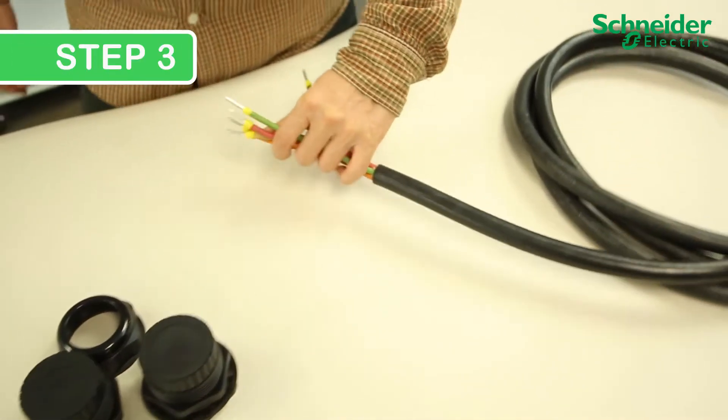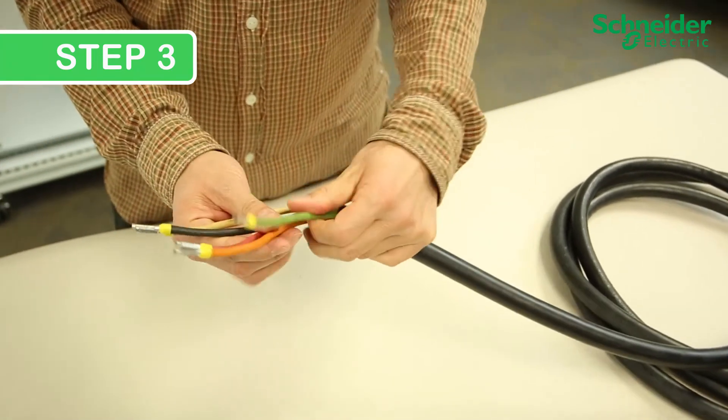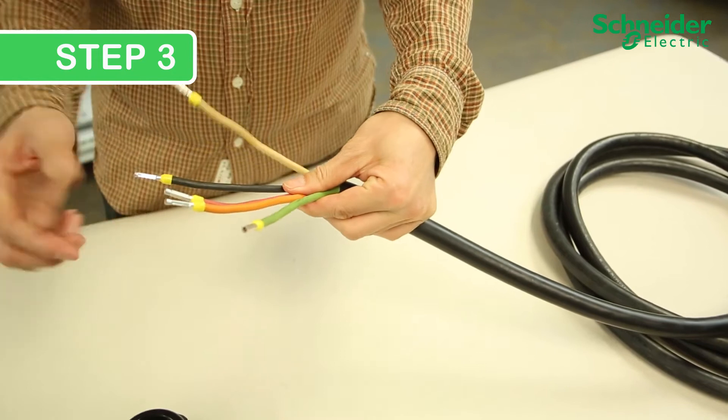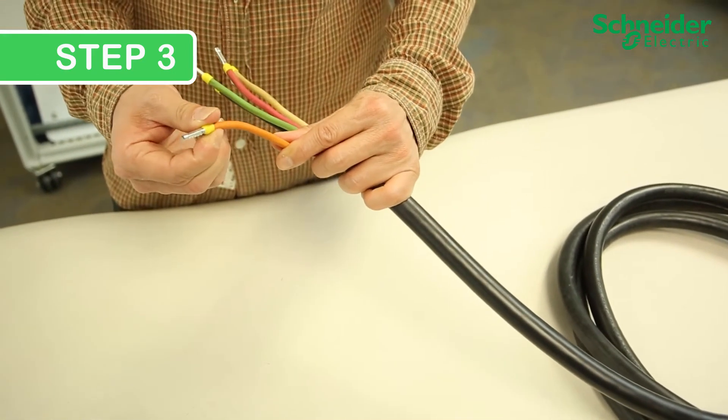Step 3: Installing AC conductors. In the CL60E, the AC cable is a 5 conductor cable with 3 lines, one neutral and one ground. Ferrules should be used for stranded wire.